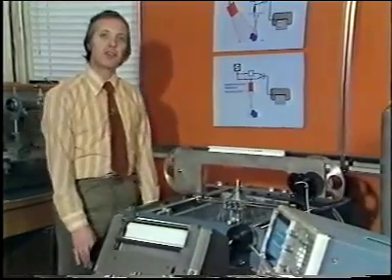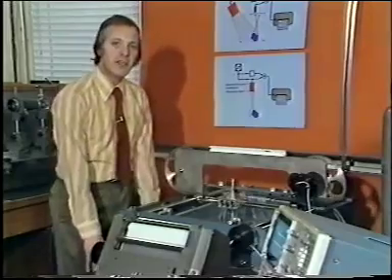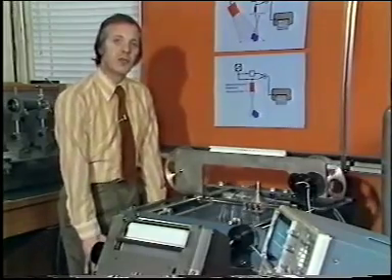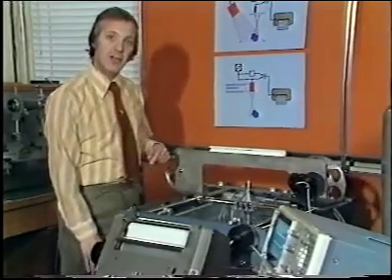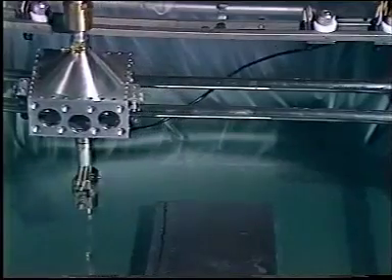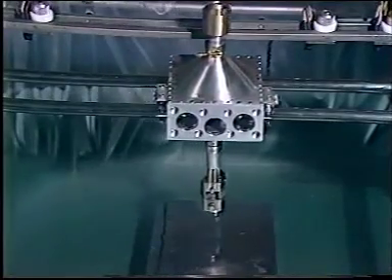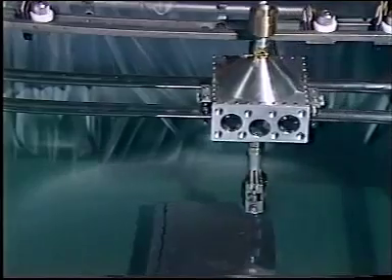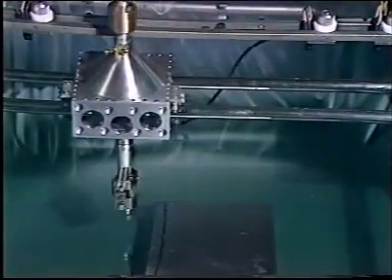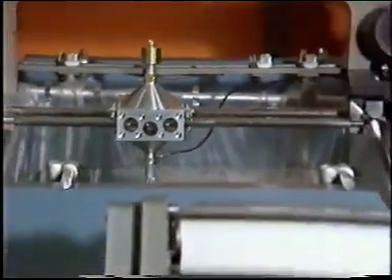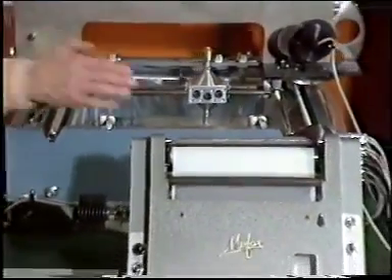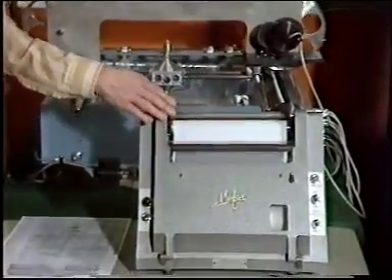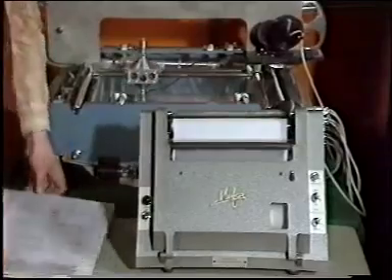Well, this is another ultrasonic machine which was developed here at the Non-Destructive Testing Centre at Harwell. In this case, it's scanning automatically, and there's a probe mounted underneath this carriage, and we're inspecting a steel block which is at the bottom of this tank, which is full of water. Another difference is that this time the output is being recorded on a chart recorder. And the complete recording looks something like this.